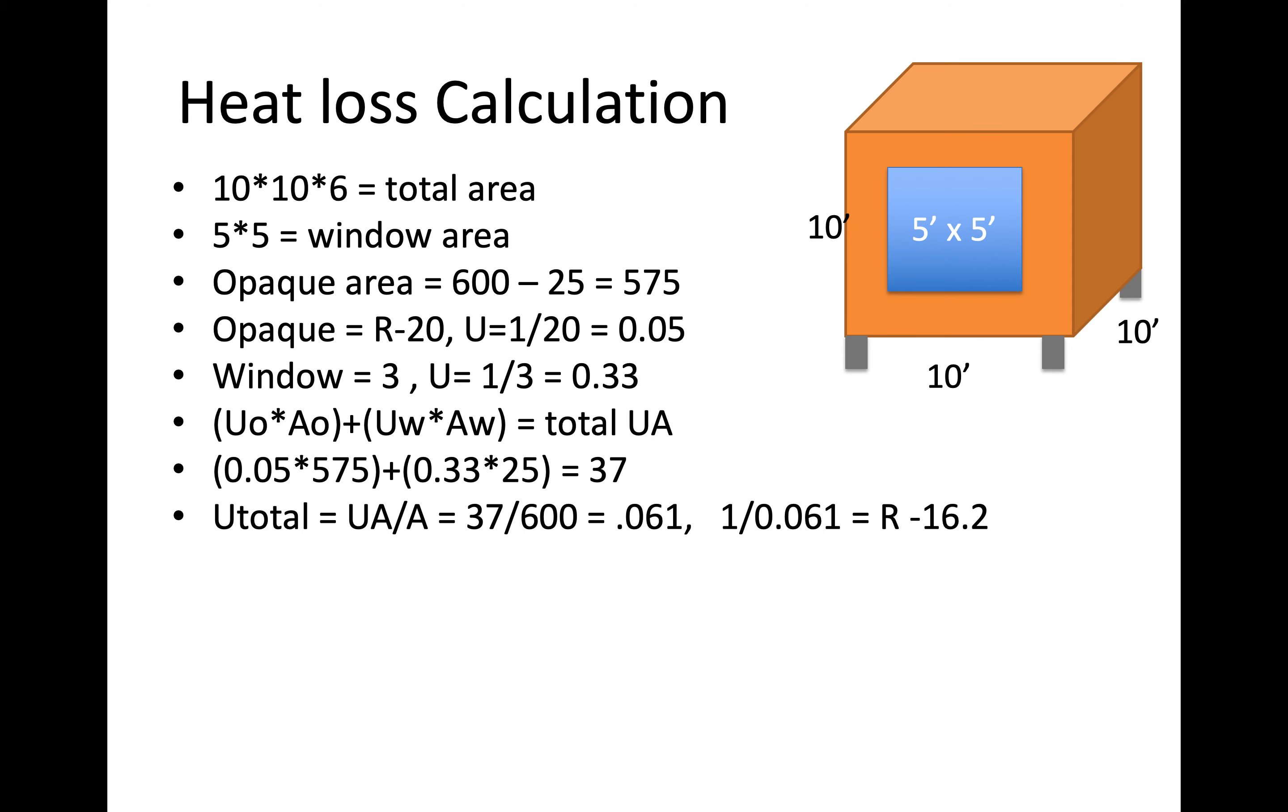Now if we wanted to find what the effective r value of that is, which I didn't actually ask in the question, we'd say take the total UA and divide that by the total area. So that's 37 divided by the total surface area of that cube, which is 600 square feet, so that's 0.061. And then the inverse of that 1 divided by 0.061, so then our r value is r16.2. So that's just how we calculate the total r value.